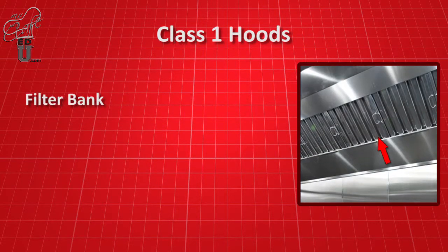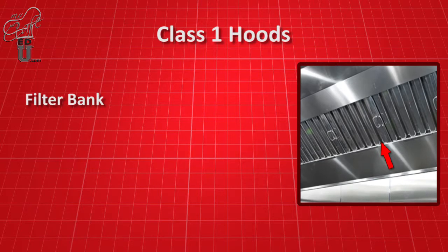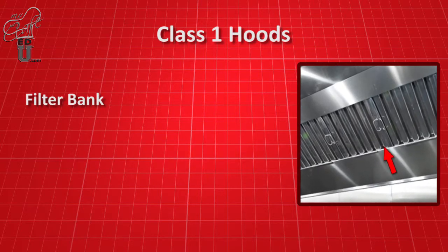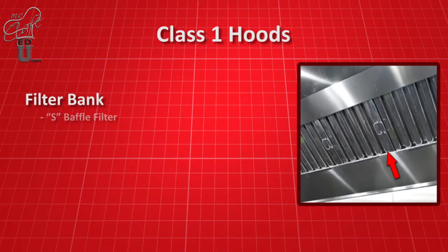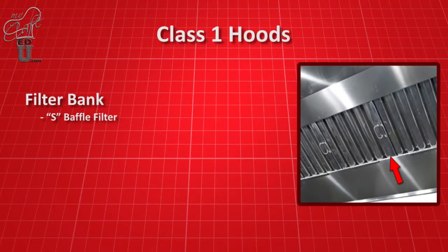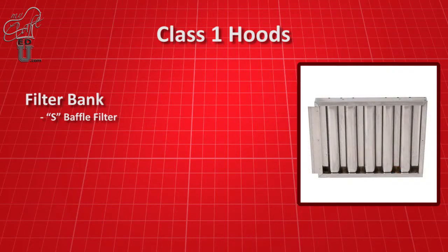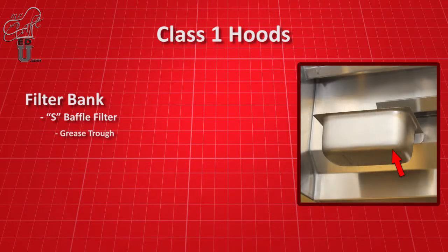The filter bank, which holds the filters in place, is installed at a 45-degree angle inside the hood. The most common filter used in Class 1 exhaust hoods is the S-baffle type. The S-baffle design essentially whips grease particles out of the airstream as the grease-laden vapor passes through the filter. The grease drains down the filter and into the grease trough. The grease trough drains the grease into the grease cup located at the end of the hood for removal.